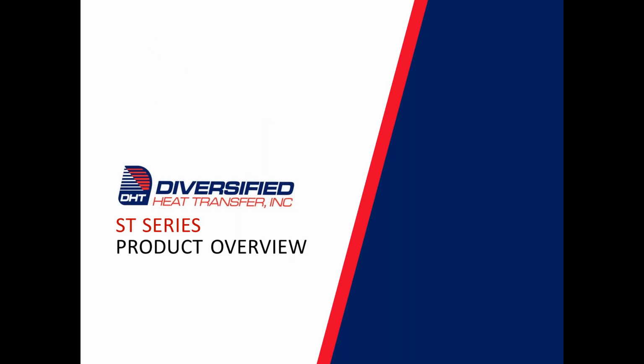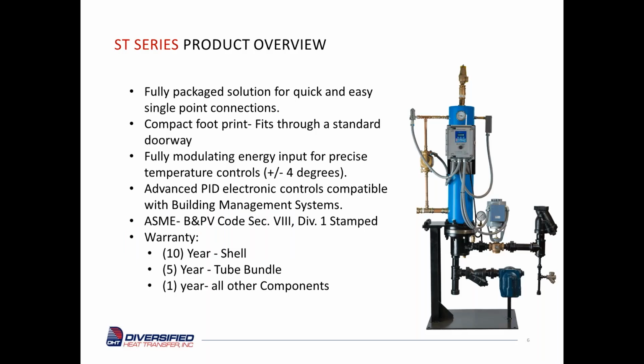So we're going to look a little closer at our SuperTherm ST Series. It's a fully packaged solution. It can fit through a doorway. It has modulating controls to modulate the steam, and we do that through our PID electronic controls. Here you see our current panel, the proportional integral derivative control panel. It also features our Diversified Heat Transfer ASME heat exchanger. The warranty on this product is 10 years on the 316 stainless shell, 5 years on the tube bundle, and 1 year on all the other components.